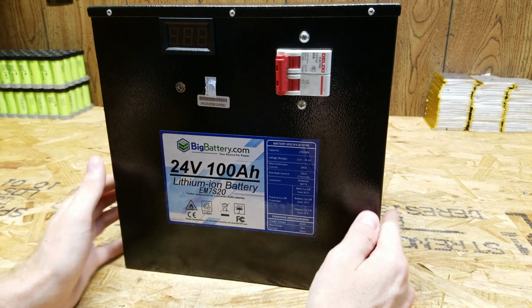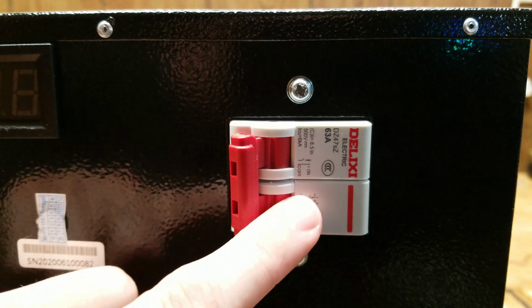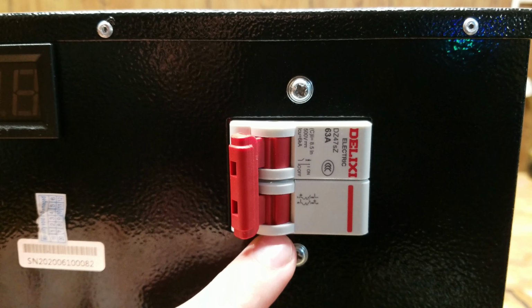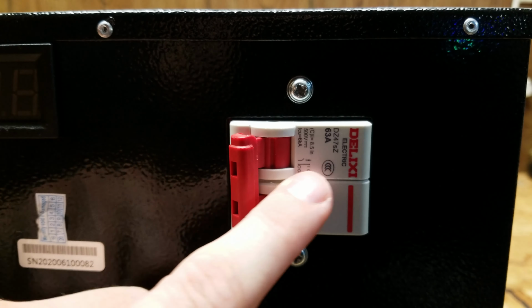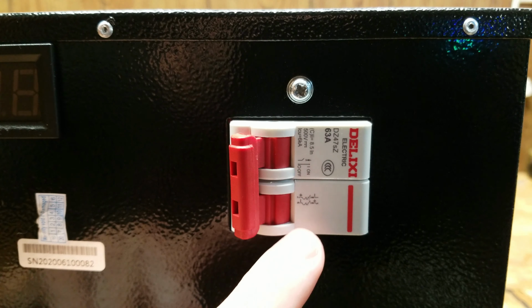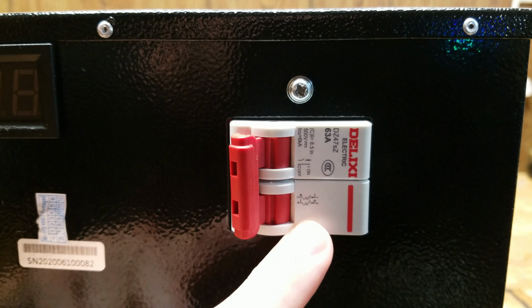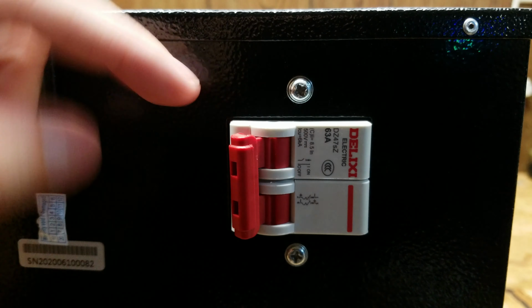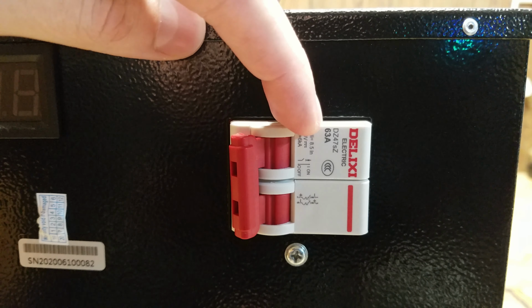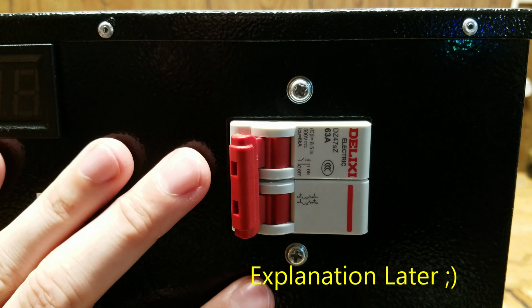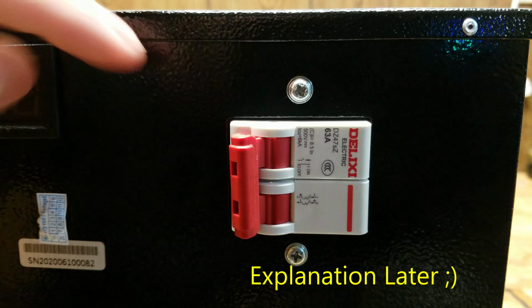But first, let's take a closer look at the device itself. In the top right here, we have a double pole circuit breaker, and it's a proper DC rated breaker, non-polarized, which is good. However, one thing I noticed is that this is a 63 amp breaker, and this device is supposed to be rated for 100 amps continuous.